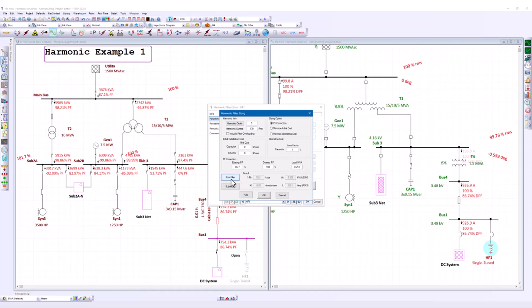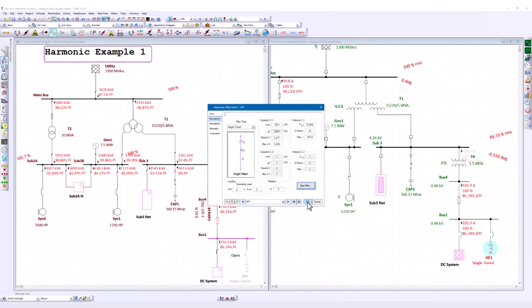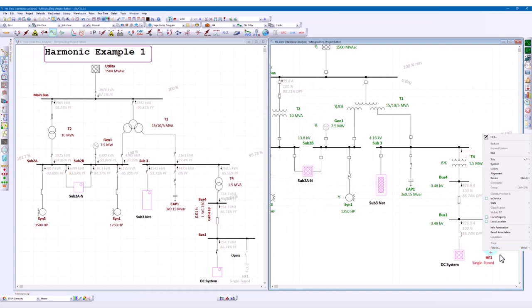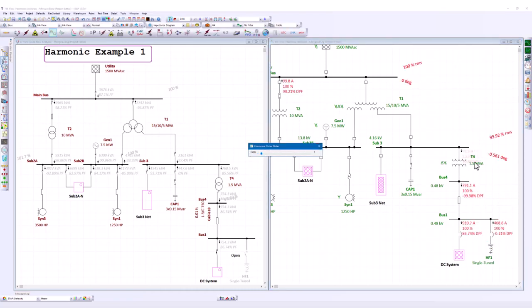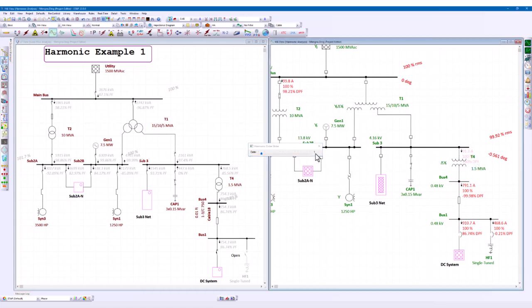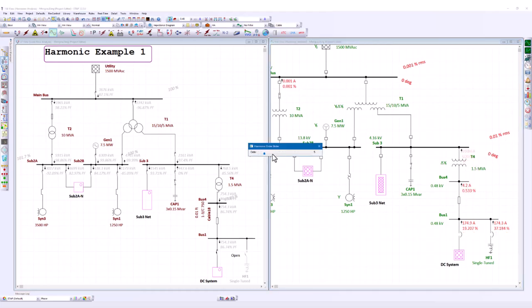Let's click on the size filter button. You will see the results are calculated, and let's click on substitute to update the filter editor with the calculated results. Now let's click OK and verify that the filter sizing is valid. Let's make the filter in service. Now if I run harmonic load flow again, first let's take a look at the power factor. When I'm at the fundamental frequency, you will see now my power factor has been corrected to 100%. And if I go to the fifth order, you will notice that the total current flowing into bus 5 used to be 170 amp. Now it is only 4.2 amp. So that indicates the sizing of my harmonic filter is valid.